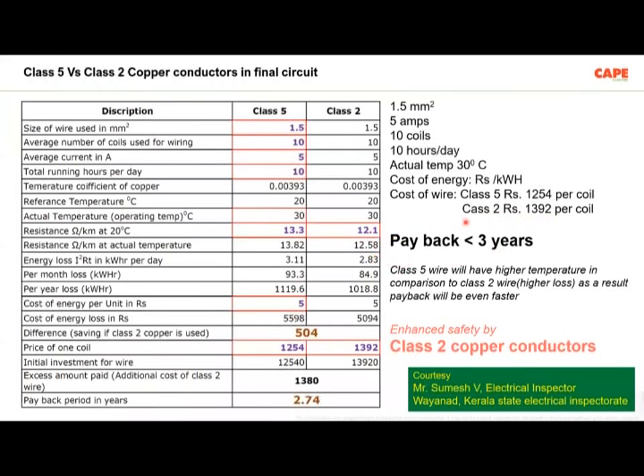Then with our calculation, we have established that the payback period is less than 3 years. So that means in an installation, if you buy class 2 conductor, of course you will be paying a little bit more, but your payback is within or less than 3 years. Now this is actually a moderate calculation, but in a practical case, if we calculate, the payback will be even faster.